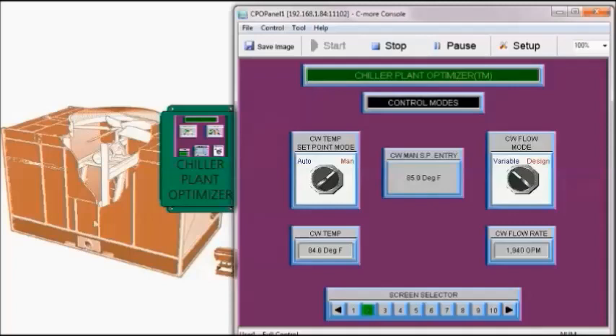And this, of course, reflects the lower system load. So, with the variable flow, the control algorithm is maintaining a 10 degree delta T between the cold and hot water temperature by controlling the flow. And we see the results.